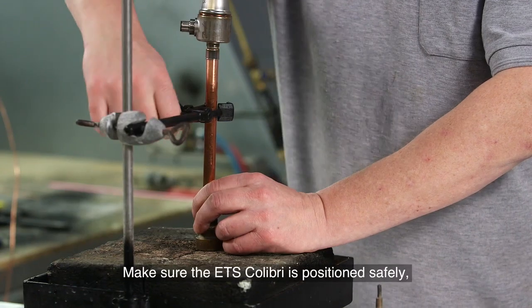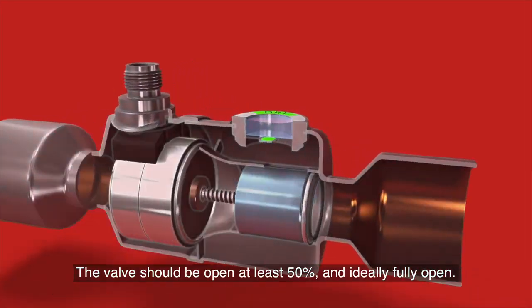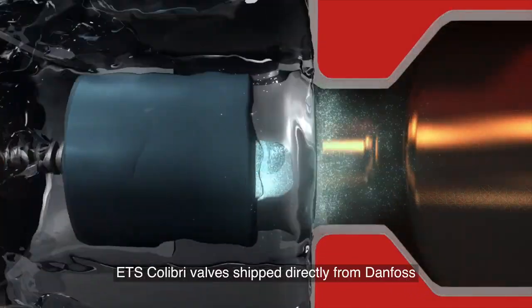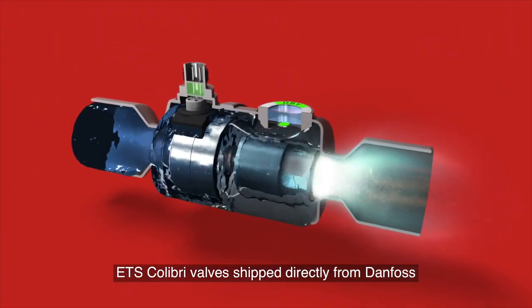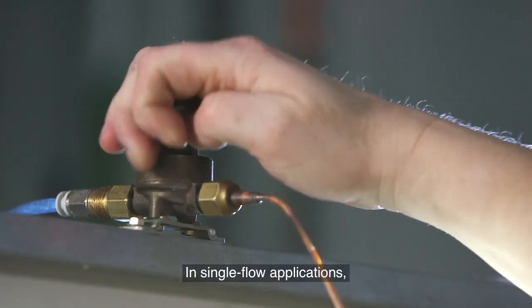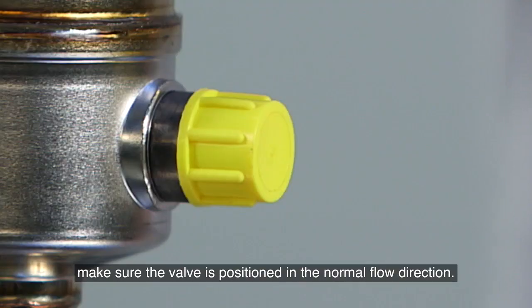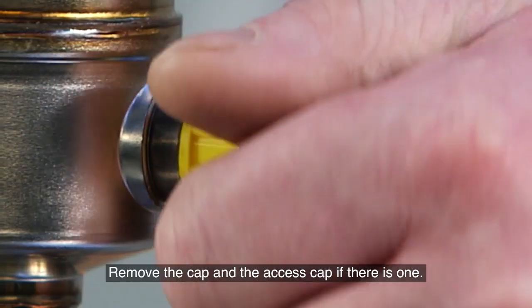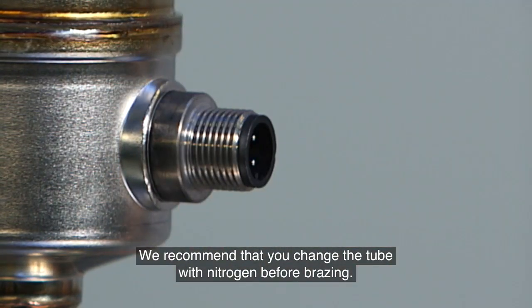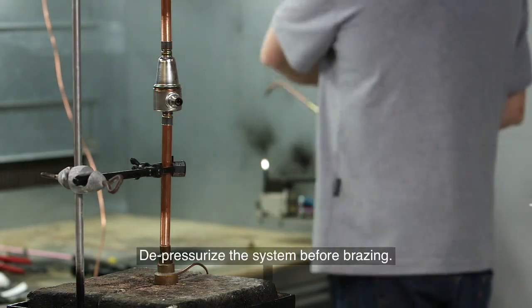Make sure the ETS Colibri is positioned safely. The valve should be open at least 50% and ideally fully open. ETS Colibri valves shipped directly from Danfoss are always fully open and ready for brazing. In single flow applications, make sure the valve is positioned in the normal flow direction. Remove the cap and the access cap if there is one. We recommend that you purge the tube with nitrogen before brazing. Depressurise the system before brazing.